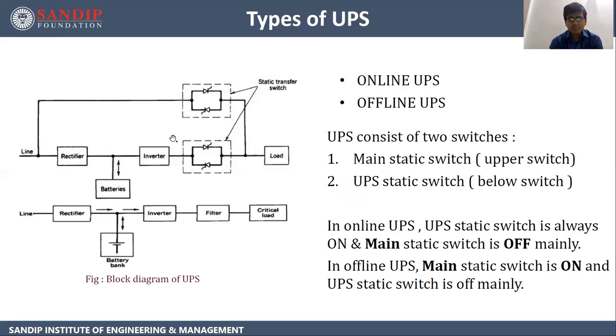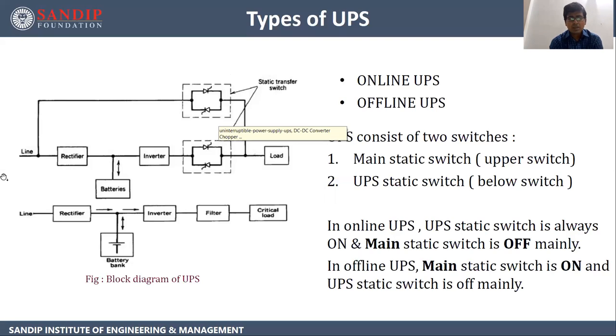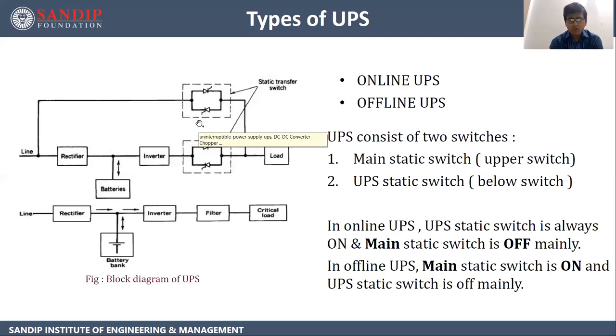In case of Offline UPS, the UPS static switch is off and the main static switch is on. So mostly this line supply directly feeds the load through this switch. Simultaneously this line supply is fed to the rectifier, which converts AC into DC, and DC is stored in the batteries. If any power failure takes place or there is a problem in the line supply, the main static switch will get off and the UPS static switch will get on. Then the power or DC stored in the battery is fed to the inverter, which converts DC into AC, and that AC feeds the load.